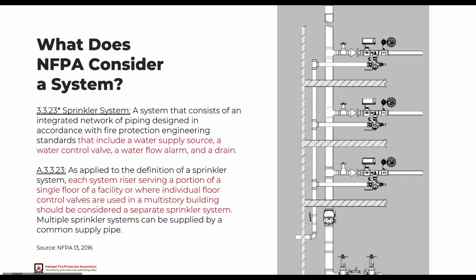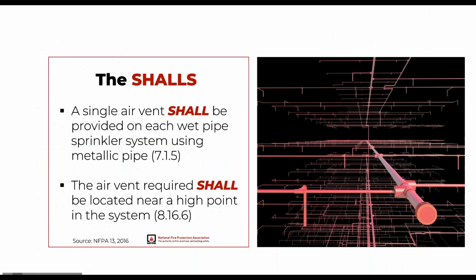You could have an authority saying that they want an air vent on each and every floor. So you have to be cautious about how you're interpreting what is a system and how many air vents you should and shouldn't have on a system. The two important shalls, and this is for all building owners and engineers: you need to have a single air vent per system, and that single air vent shall be located near a high point in the system.